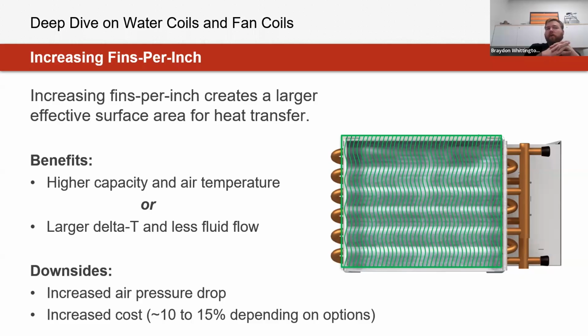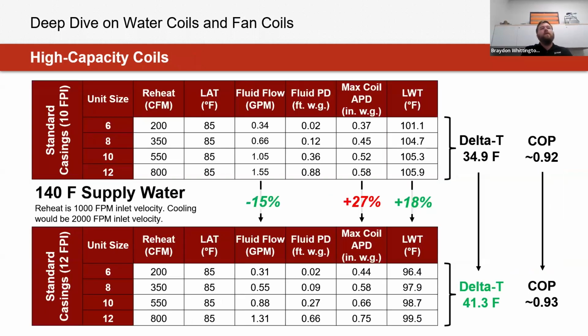But one key consideration if we are bumping up our fins per inch is the additional amount of air pressure drop that's going to be added to our system. An example of this when evaluating at 140 degree supply water temperature is that we are able to achieve, or maximize, what that water side delta temperature is going to be, which could be more ideal for condensing boiler systems. But one trade-off when looking at increasing fin density, whether it be for a single duct unit or once we start looking at fan coil equipment or even just standalone coils, is just the reality of additional pressure drop adding to our system there. So one way to highlight this is that as you start to play around with the fin density of a coil, this does have an influence on how much capacity it's going to provide as well.